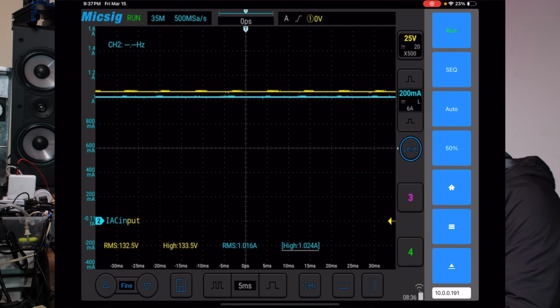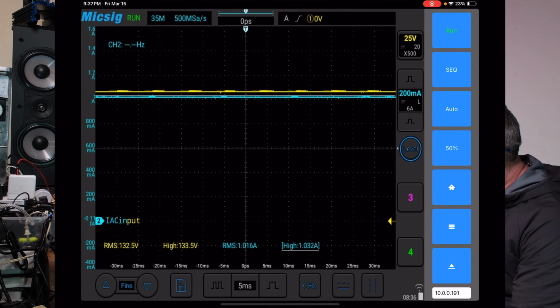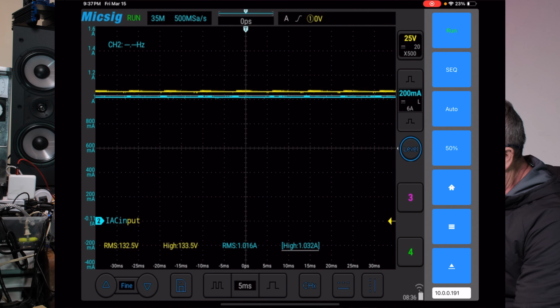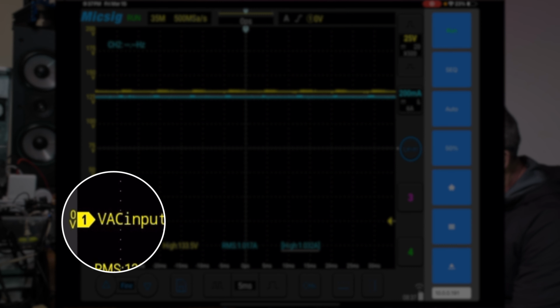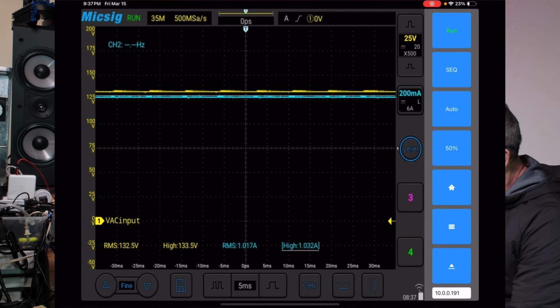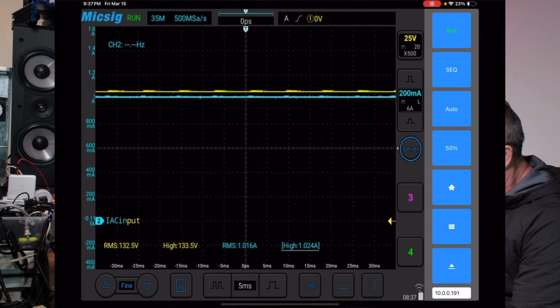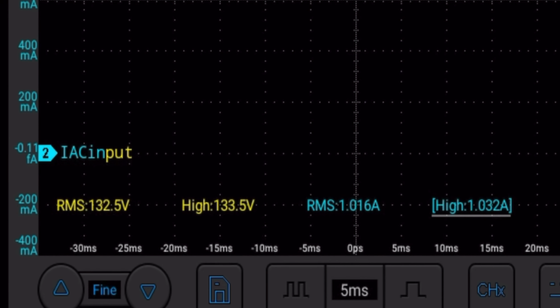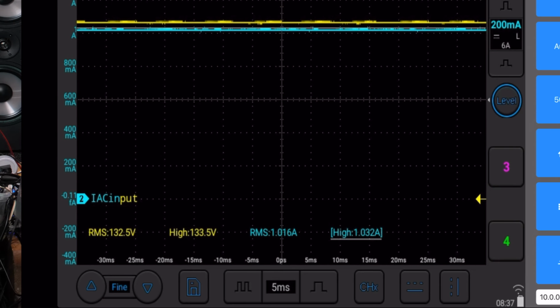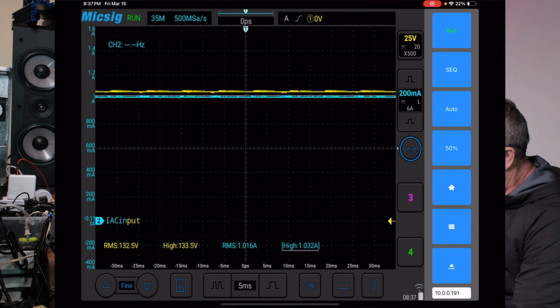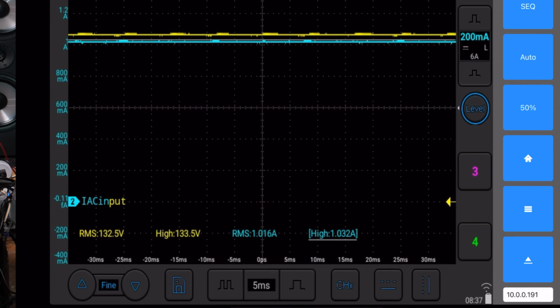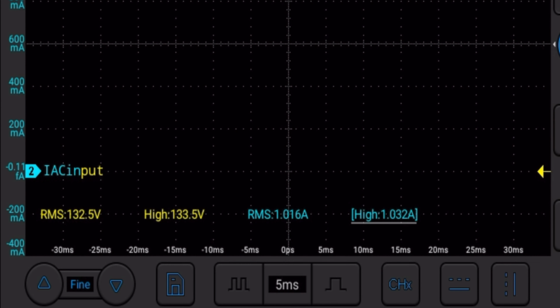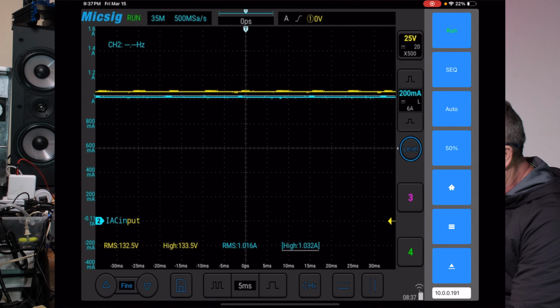Let's do it. So now what we're doing is looking at the output, and we have 25 volts per division, you can see the marker down here. I've got the current and voltage marker right on top of each other. Here I touched it, you can see the voltage marker there, the current marker there, and the waveforms again look very even. The measurements down below, RMS for voltage is 132.5, high is 133.5, so again looks like about 1 volt ripple maybe. Then the current, RMS and high are almost the same - high is a little bit higher, but you can tell the ripple current's going to be very low.